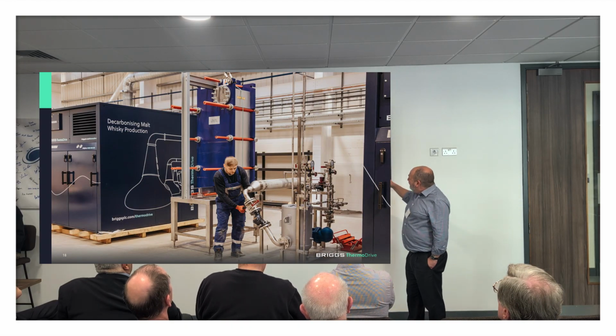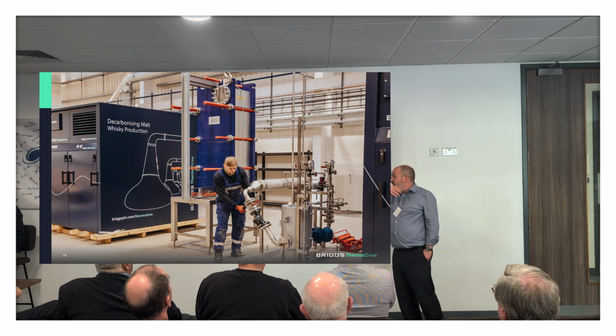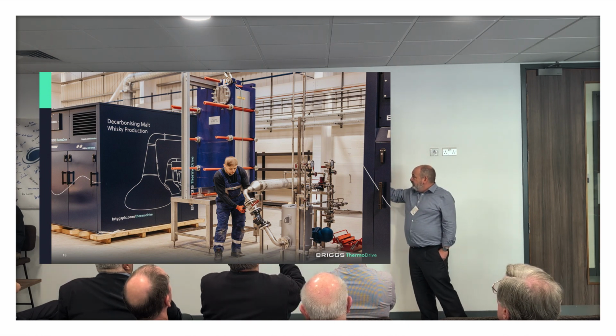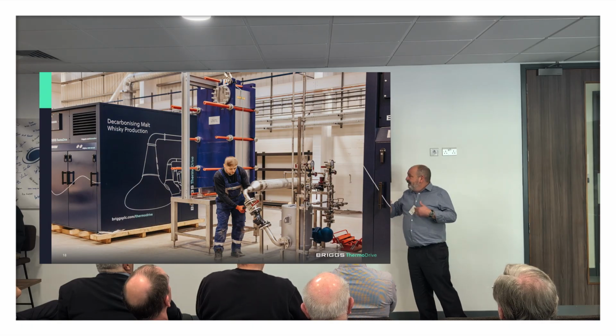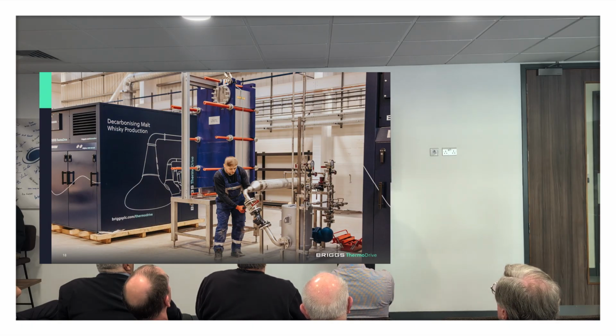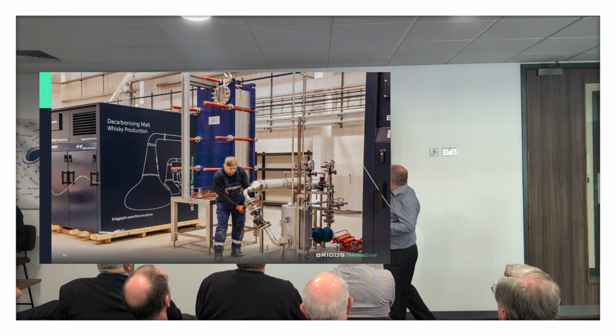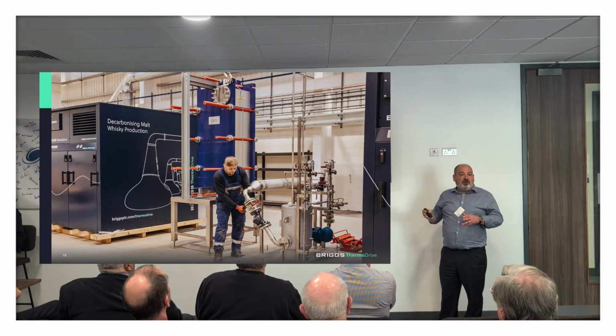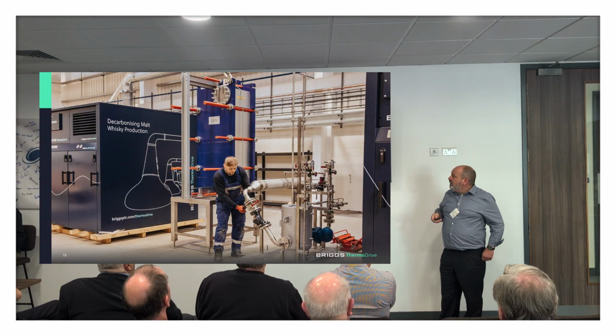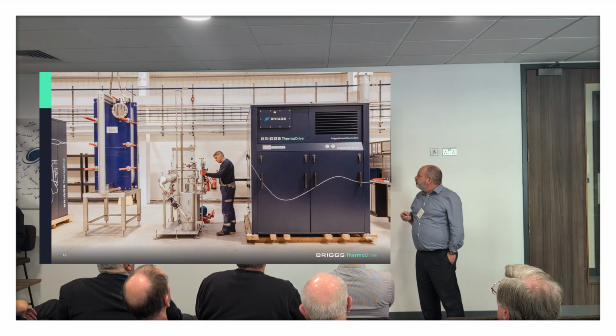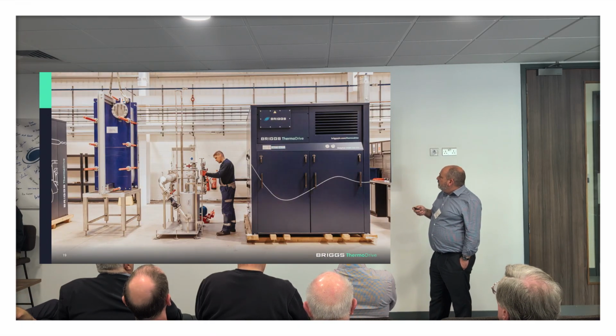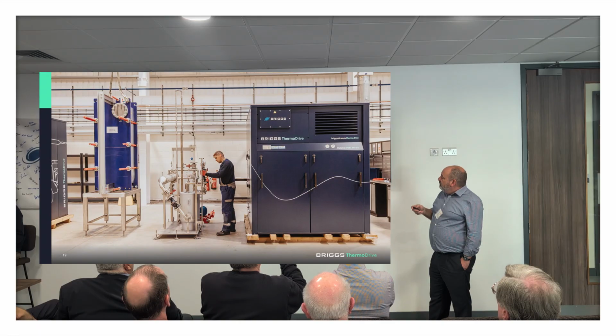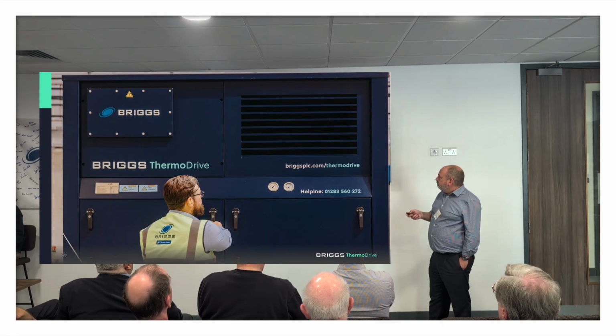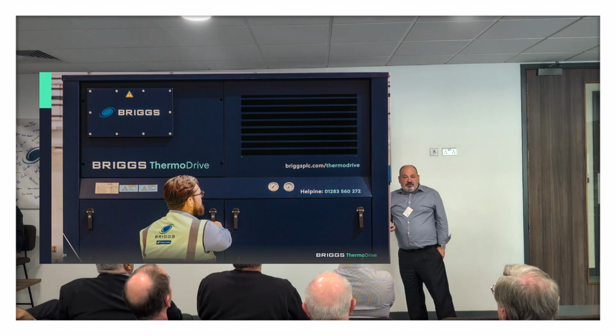Typically, condensate is driven back to the boiler house using steam pressure, and again, I'm generating that steam pressure through the compressor, so I don't want to do that. For the actual condensate pumping, we have mechanical pumping units rather than relying on the steam pressure. You can see those units which were being finished off the other day. And our single point of contact.